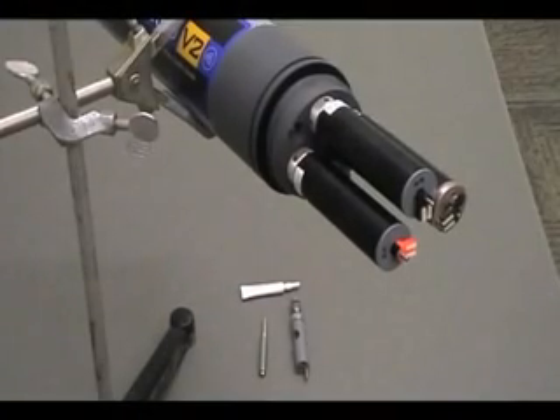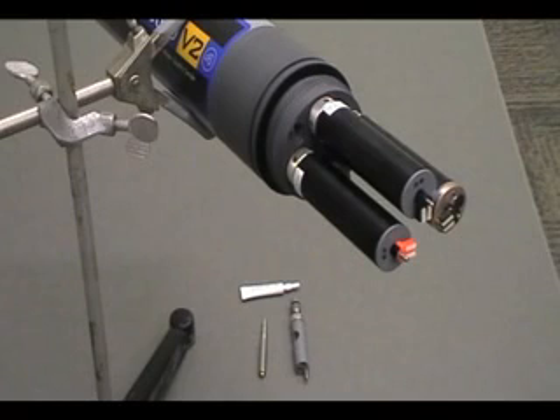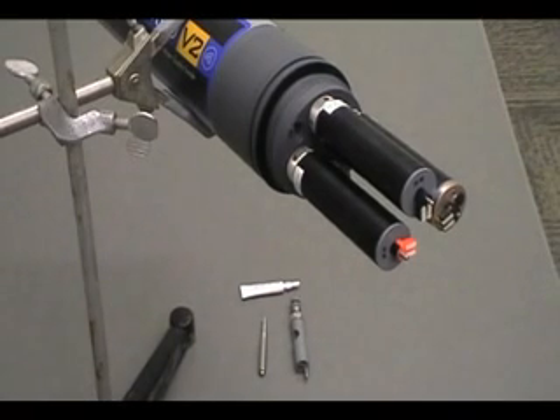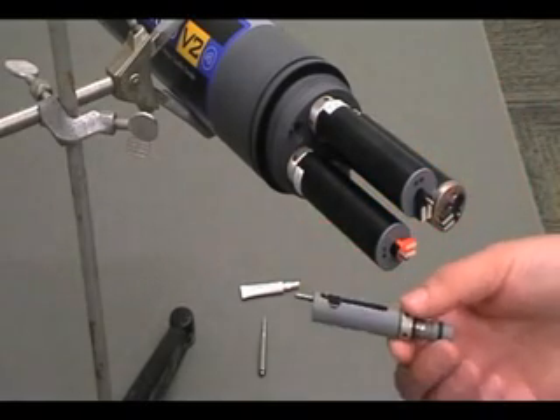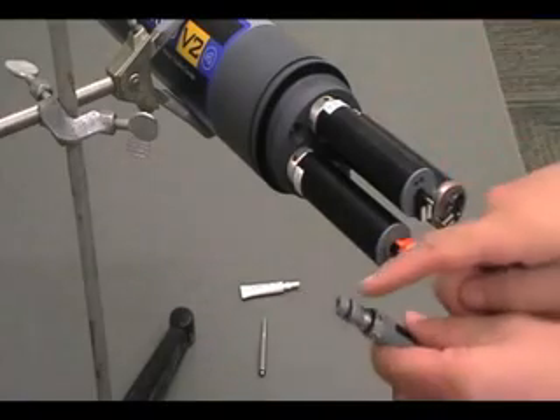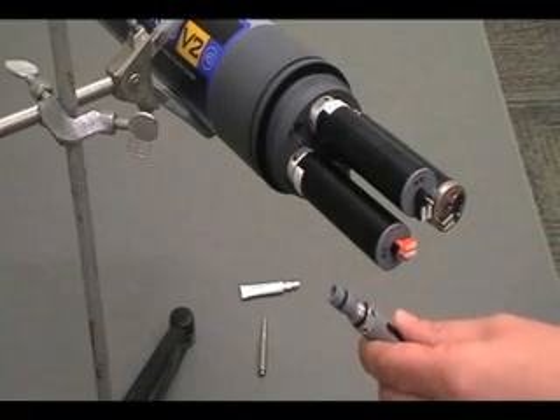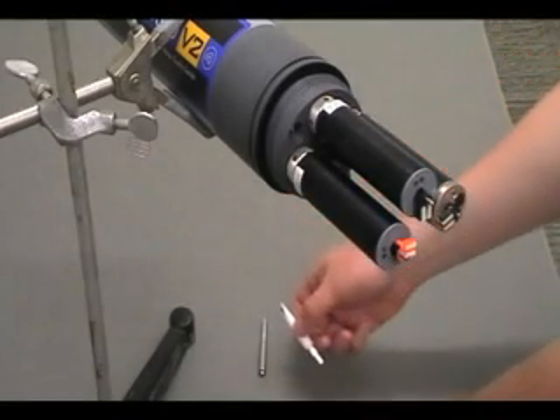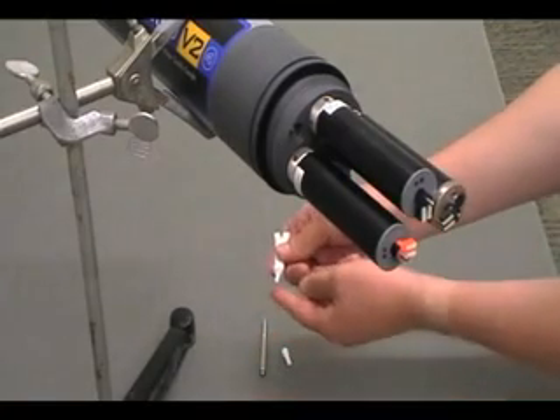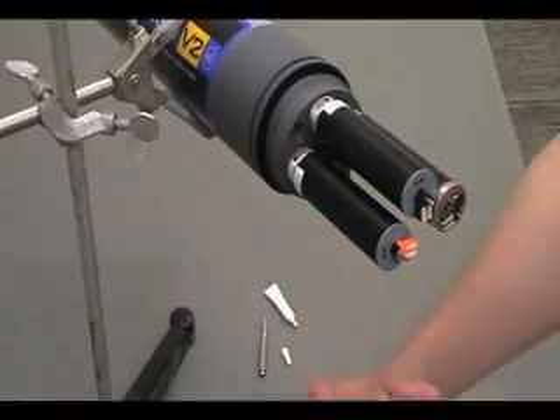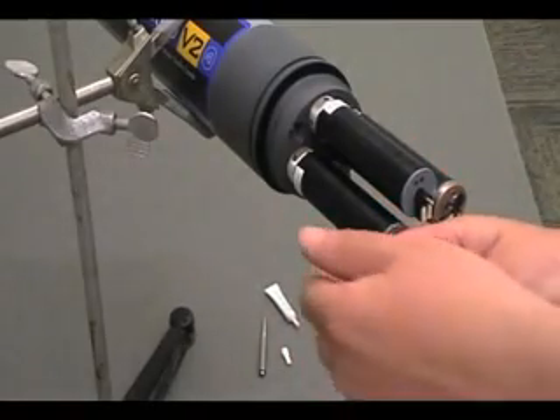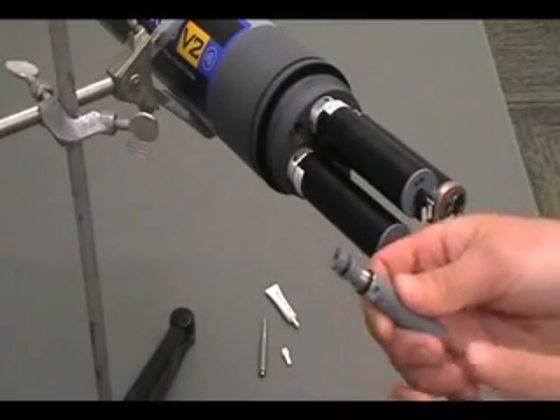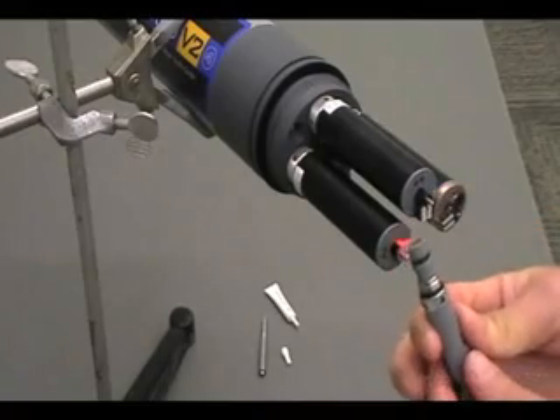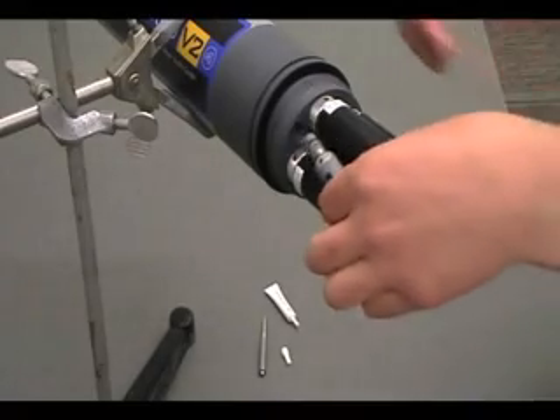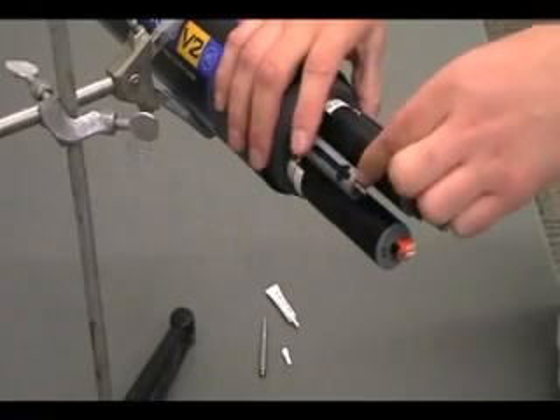Installing regular sensors. Install regular sensors after the optical sensors. As an example of how to insert a regular sensor, we will install the conductivity and temperature sensor. Ensure that the O-ring on the sensor you are inserting is completely clean of dirt. Apply a very light sheen of Krytox to the clean O-ring. Insert the sensor into the appropriate port, in this case the 6-pin port, and gently rotate until the pins of the connectors are aligned.